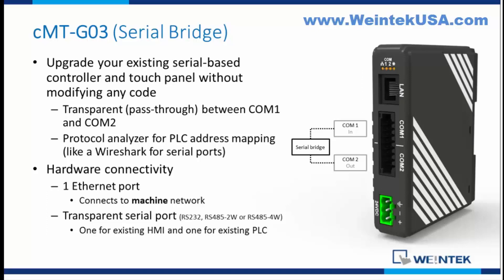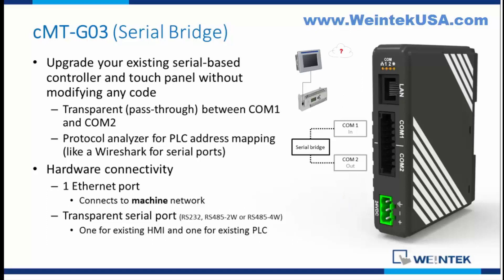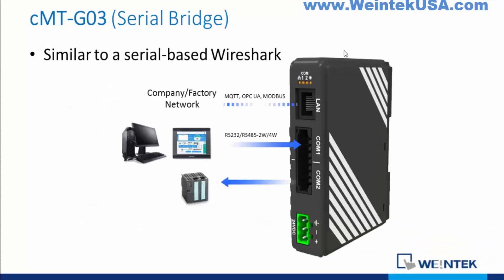One of the newer models, the cMT-G03, features a serial bridge. Here's a scenario: let's say you had an Allen Bradley PLC talking to a PanelView, and it's an old system — all serial, no Ethernet. And you need to collect data from that system, monitor alarms, and synchronize them to a newer SCADA system or to a database. All you would need to do is simply cut the serial cable in half. We provide a very nice push-lock connector, and this wire-taps into the system. It's very low impact and easy to integrate into an existing system, overcoming the problems of adding new communication devices to old equipment.